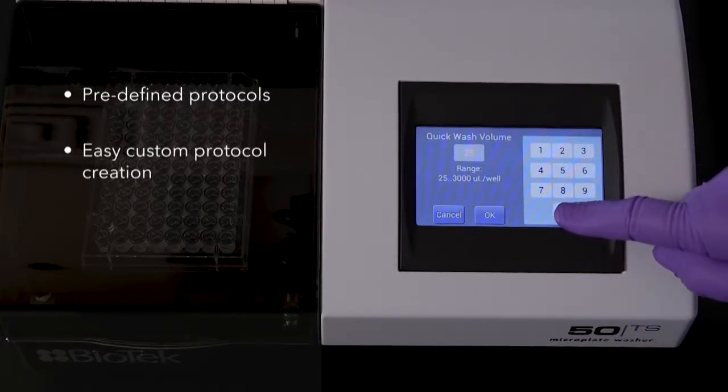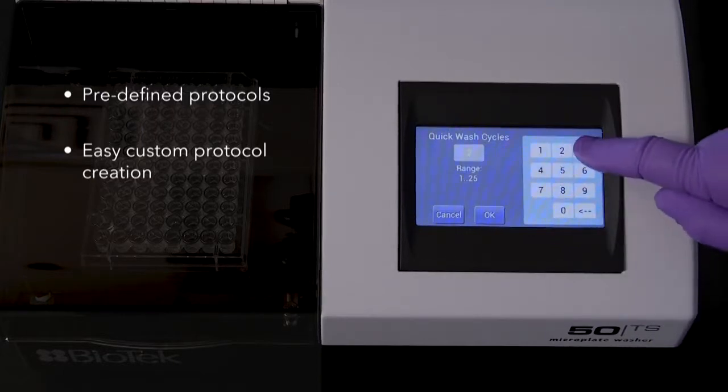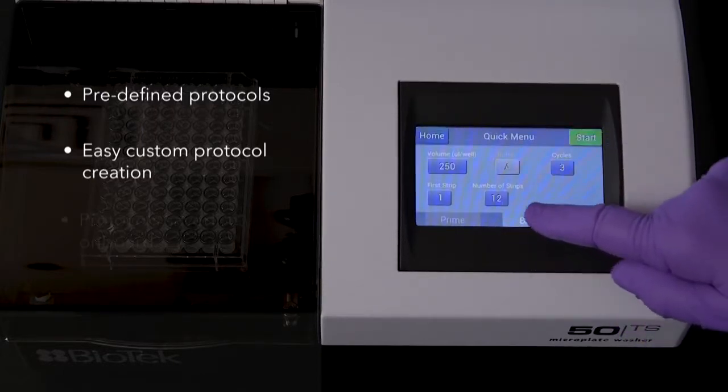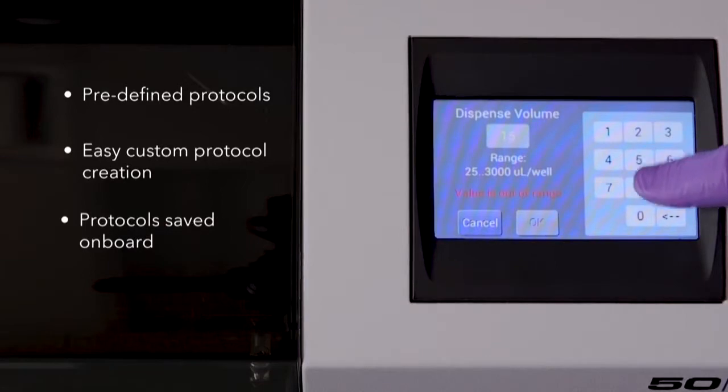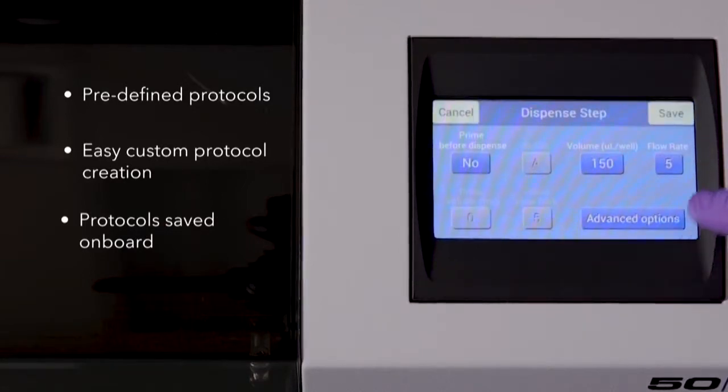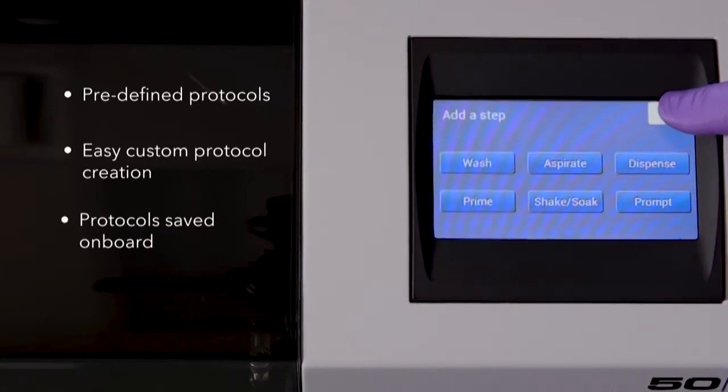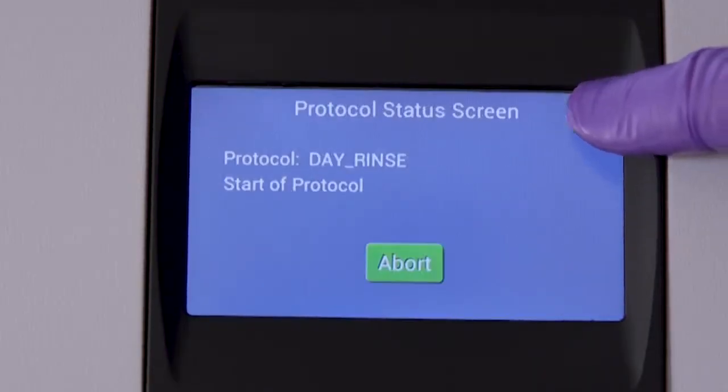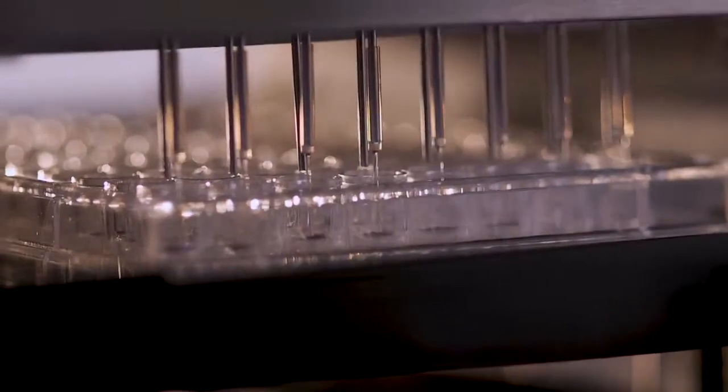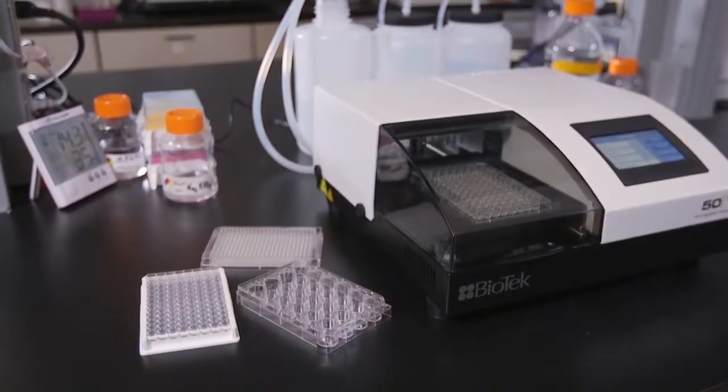Creating custom protocols onboard the 50TS is easy. The touch screen and menu driven software make multi-step program creation intuitive and simple. Protocols are saved for quick recall. Just touch start and the 50TS washes a single strip to a full plate quickly, efficiently and reliably.